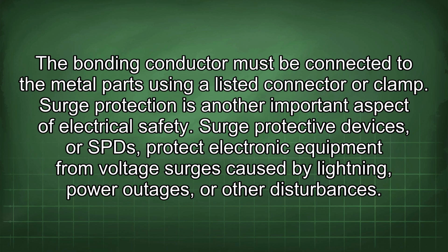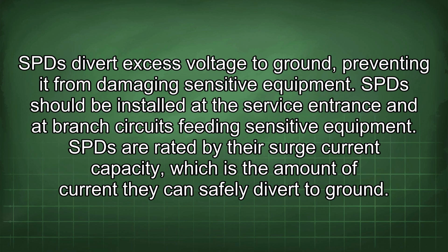Surge protection is another important aspect of electrical safety. Surge protective devices, or SPDs, protect electronic equipment from voltage surges caused by lightning, power outages, or other disturbances. SPDs divert excess voltage to ground, preventing it from damaging sensitive equipment. SPDs should be installed at the service entrance and at branch circuits feeding sensitive equipment.